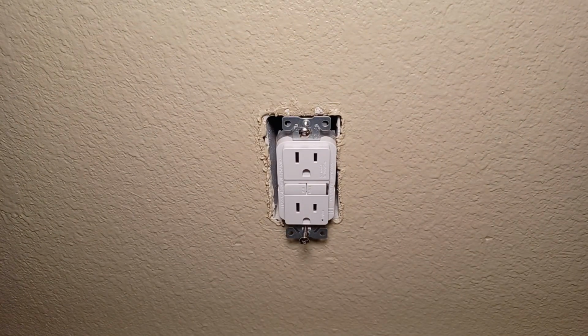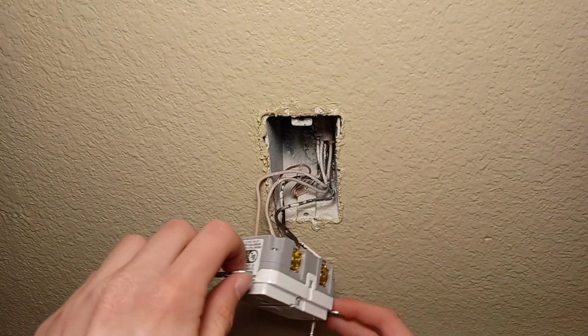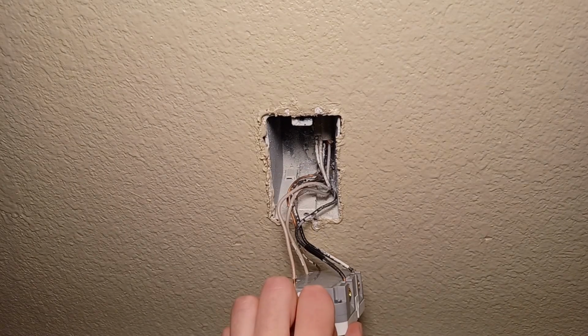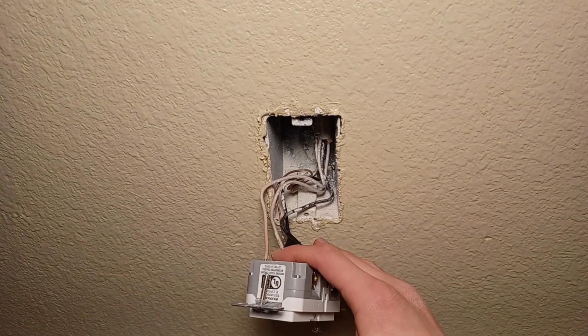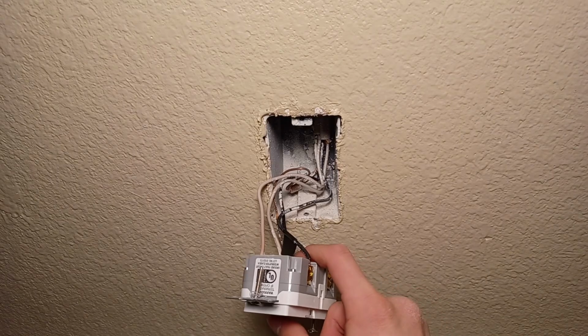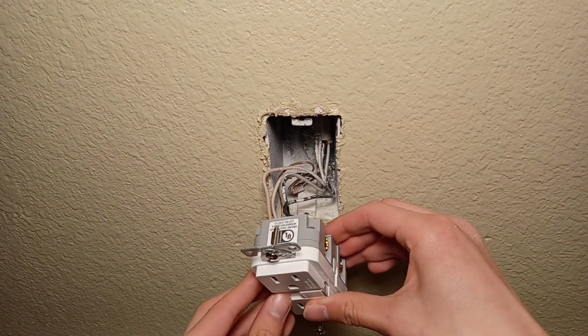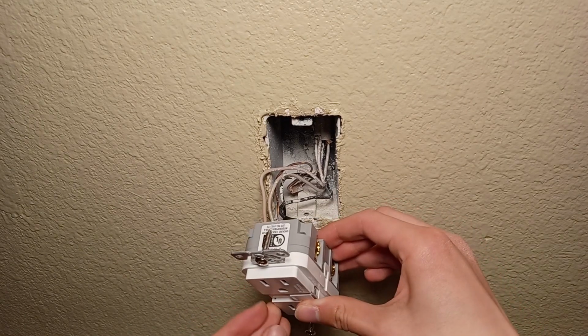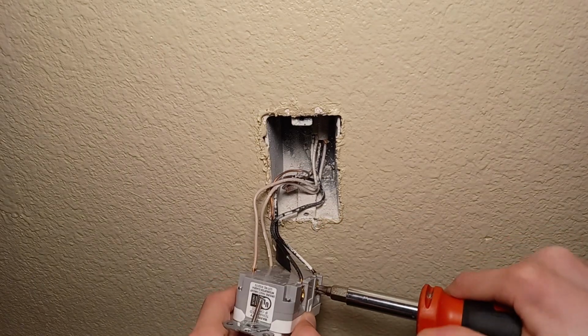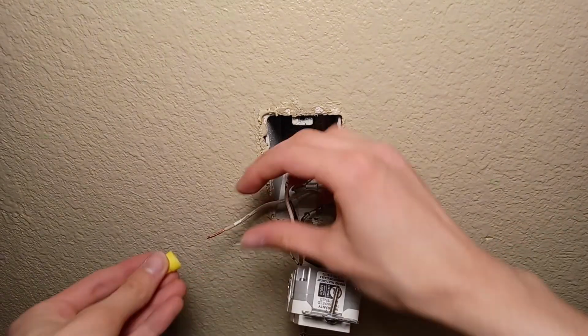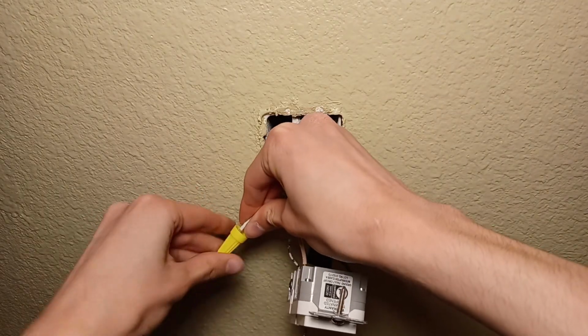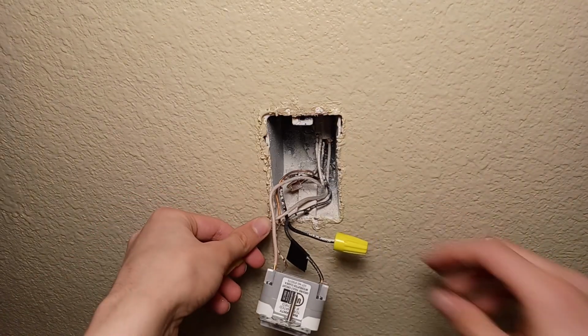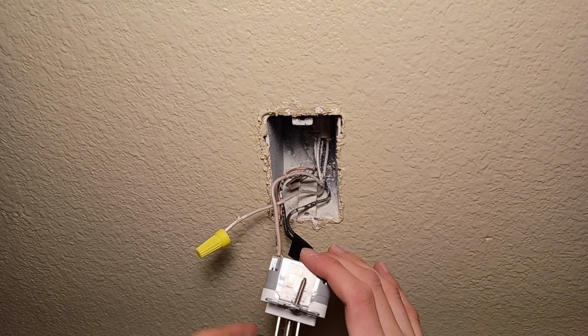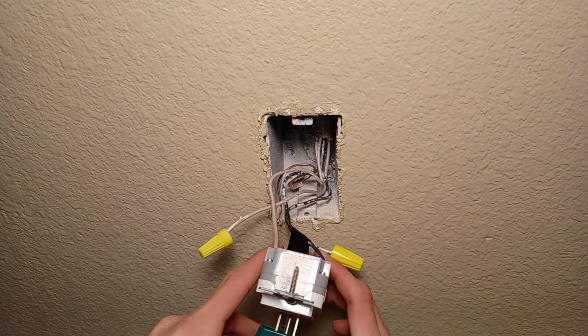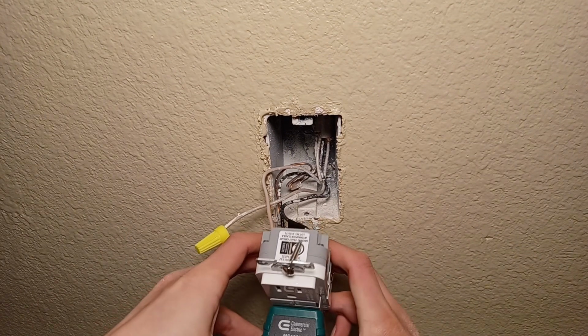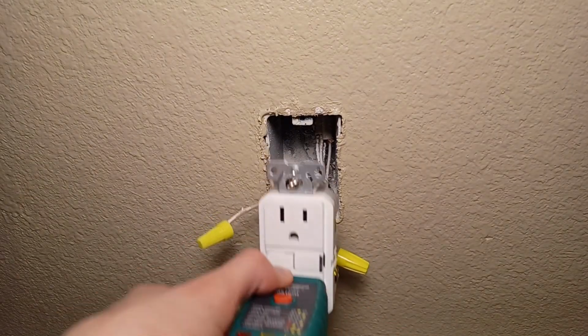Let's take this apart. Nothing is shorted. It's nothing crossed over. It's got warm. It is defective. Oh. That sticks. I got a bad unit possibly. I'm gonna remove the load side. Now the load side is completely disconnected. Now for sketchiness, I'm gonna plug in my tester first. If it trips with the tester in, then we know it's the tester.